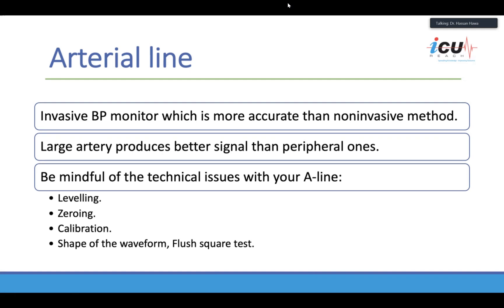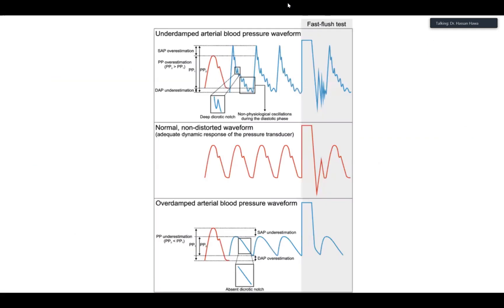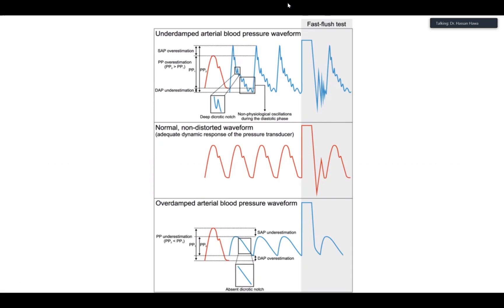If you look at the shape of the waveform and do a flush square test, you should get one or two oscillations — that's the normal state. However, if you get too many oscillations, that means your circuit is underdamped. If you don't get any oscillation at all, the circuit is probably overdamped. Usually just flushing the tubes deals with the problem.